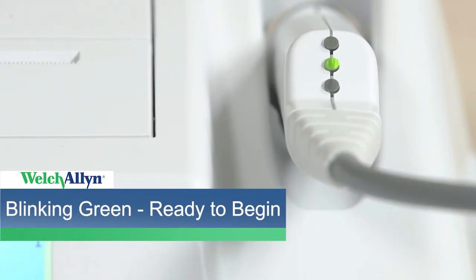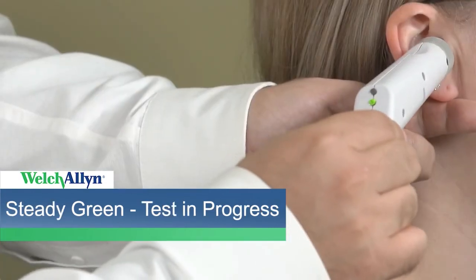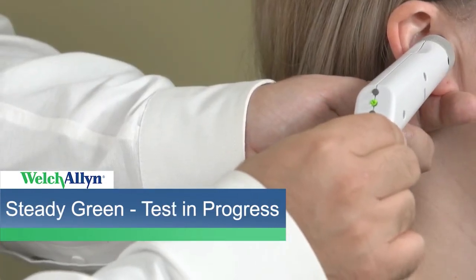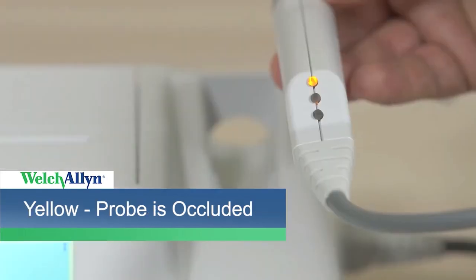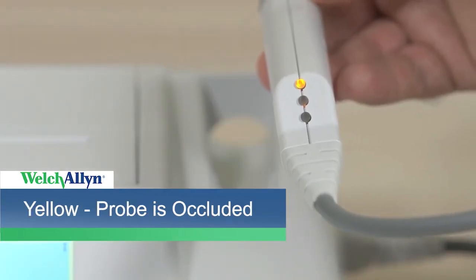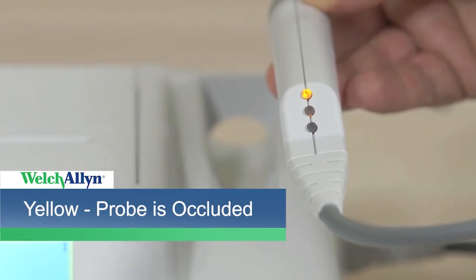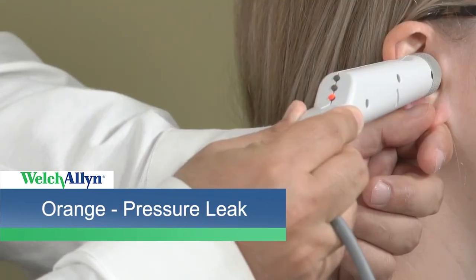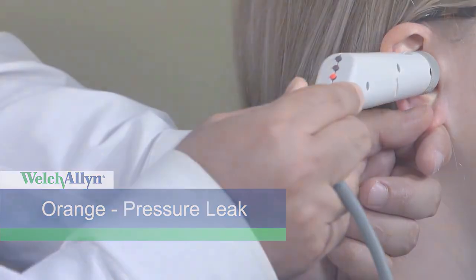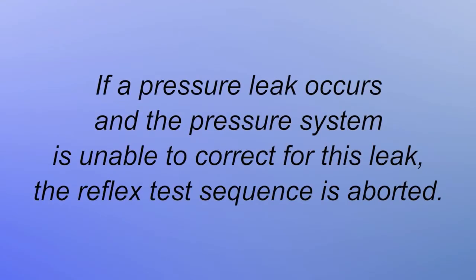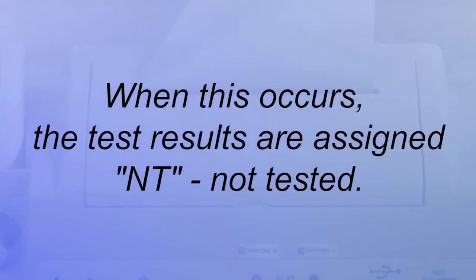A blinking green light means the instrument is ready to begin a tympanometry test. A steady green light means a test successfully started and is in progress. A yellow light indicates the probe is occluded. Remove the probe and inspect for cause of occlusion. If you see an orange light, a pressure leak has been detected. If a pressure leak occurs during the reflex testing and the pressure system is unable to correct for this leak, the reflex test sequence is aborted. When this occurs, the test results are assigned the letters NT, not tested.